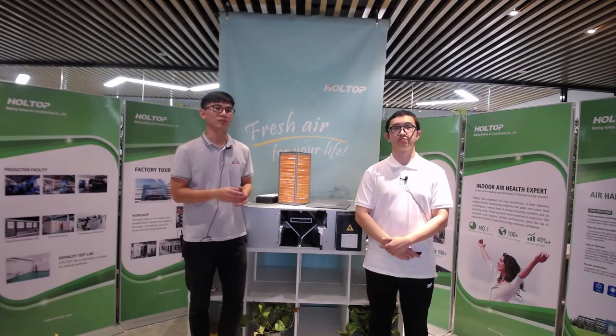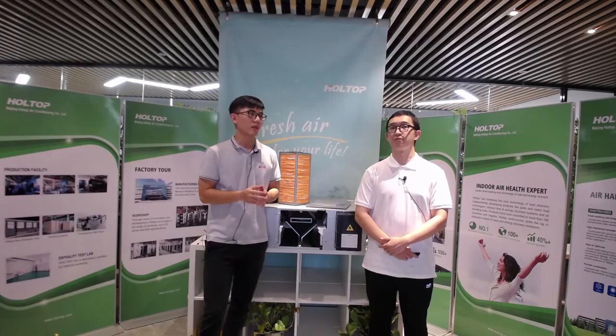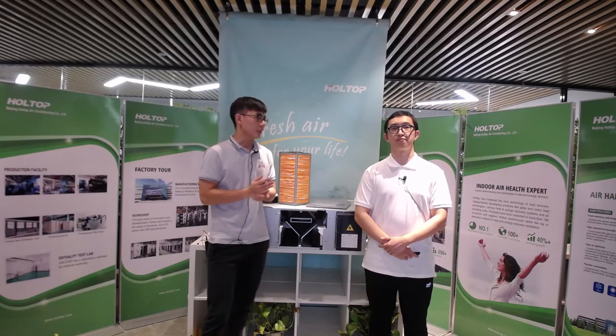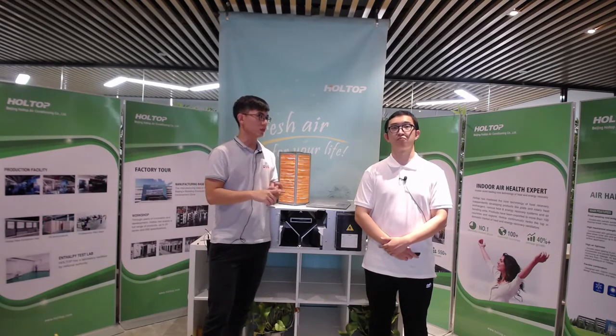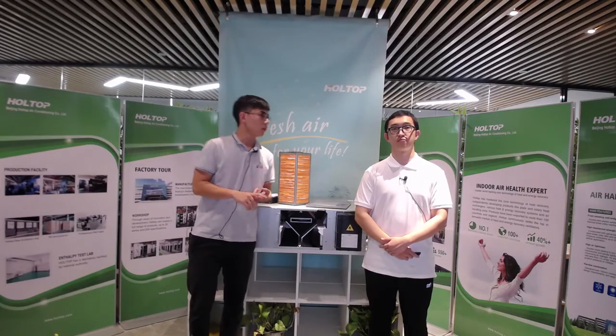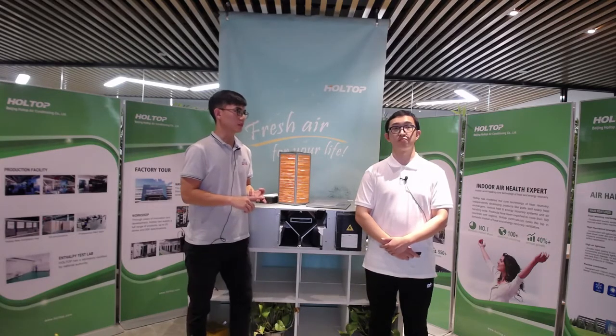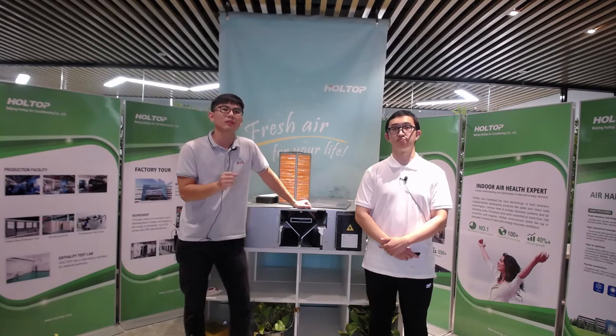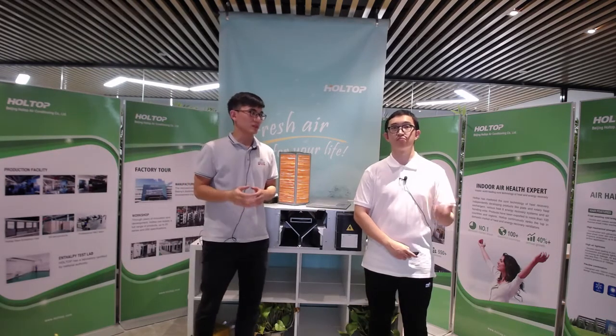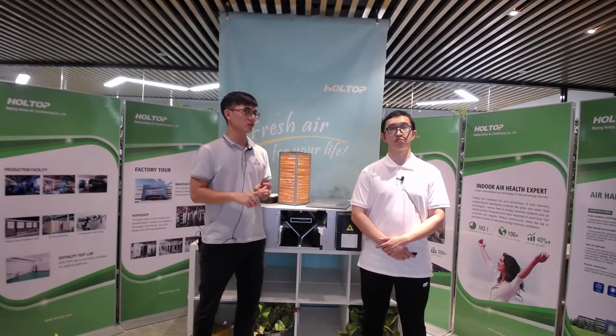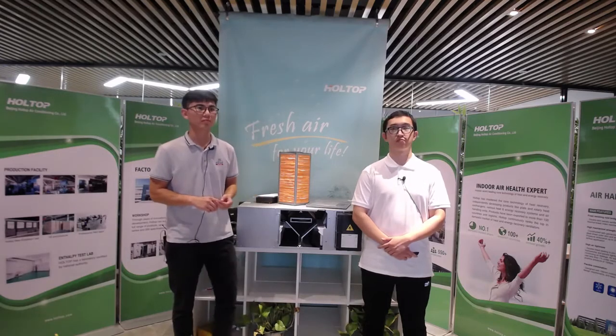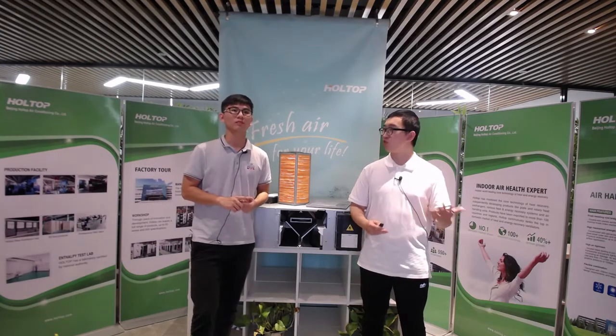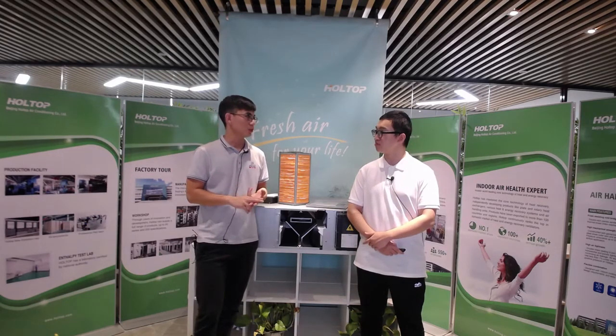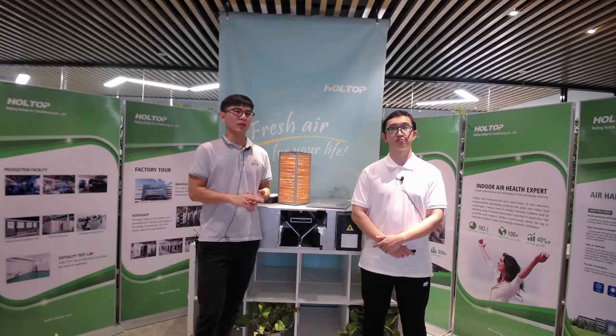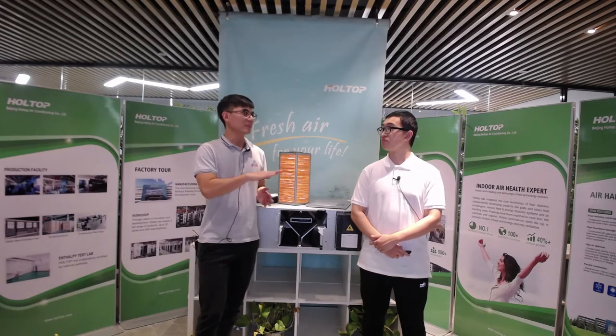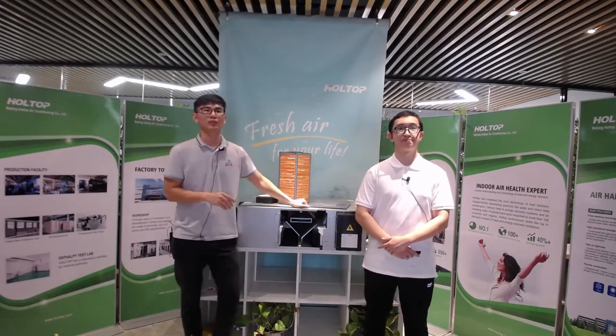Sensor control means that the ERV can run accordingly with CO2 sensors or humidity sensors. When the CO2 concentration or the humidity level is above the setting value, the machine will run at full speed to get rid of the extra CO2 or humidity. Okay, so what more functions do we have? Well, just like I said, we have so much more. So we have taken a video earlier to introduce the new functions. Yes. Okay. So Winnie, can you play the...